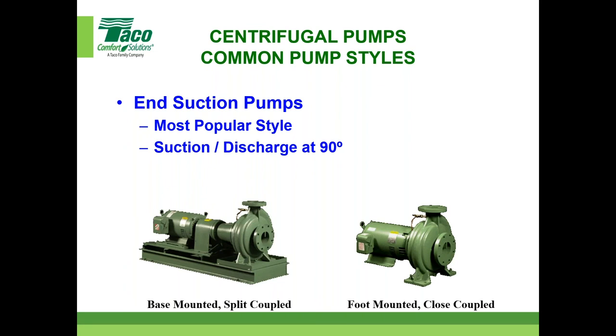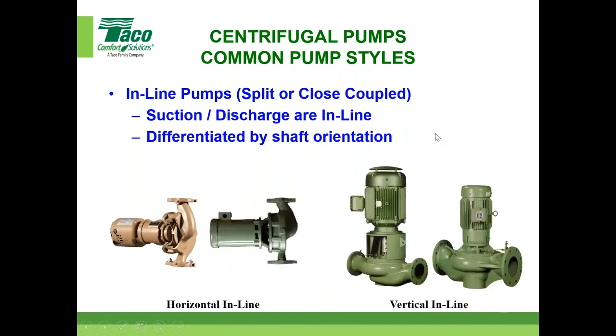So I think we have time for one last question, Brett. And the question is, is the warranty void if you do not use laser alignment on startup? I can answer that question. No, the warranty is not void if you do not use laser alignment on startup. However, the installation and operation manual indicates that the alignment should be within 5/1000ths of an inch in both the horizontal and the vertical planes. And a highly skilled technician can align motor and pump shafts to be within 5/1000ths of an inch if they're using a dial indicator, for example. But no, you don't have to use laser alignment for the warranty, but you do have to make sure that it's aligned within 5/1000ths of an inch.